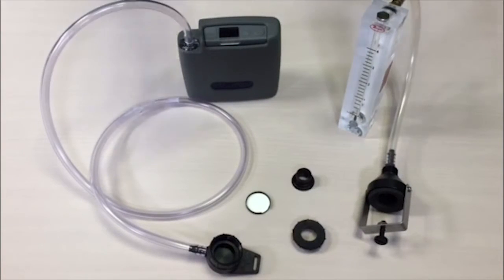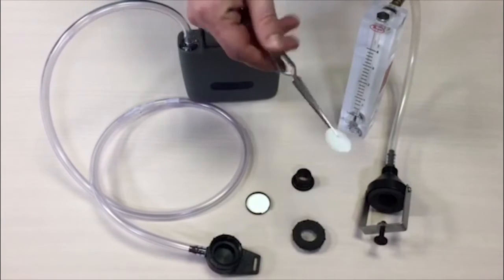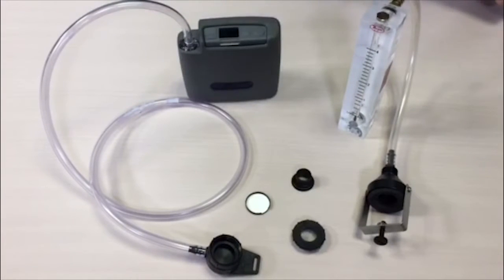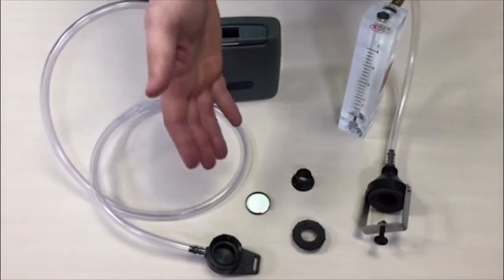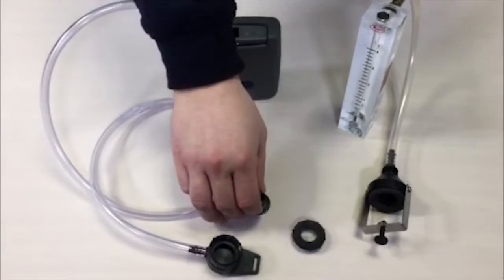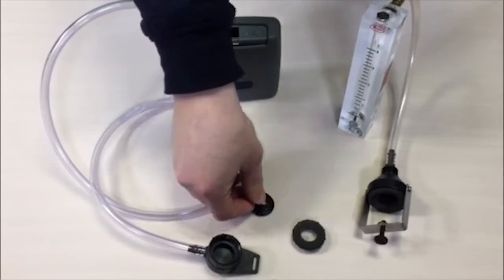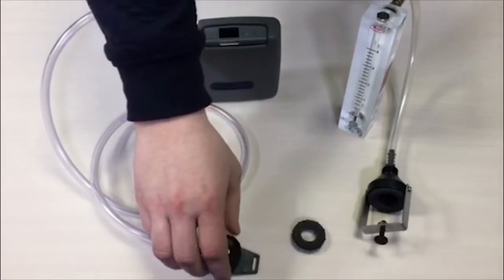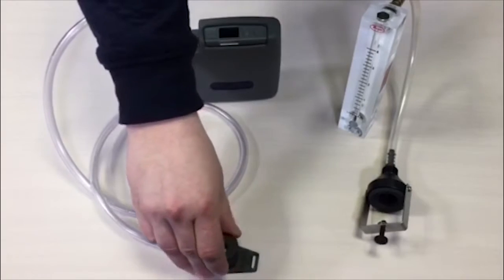The pump should be calibrated with the filter already in the sampling head. Care should be taken with the filter as they are all pre-weighed, so it should be done in a clean environment, and use tweezers to handle the filter and ensure it isn't damaged. Filters are housed in a cassette which is then assembled to go in the sampling head. Once assembled, ensure it is securely tightened and fastened together.